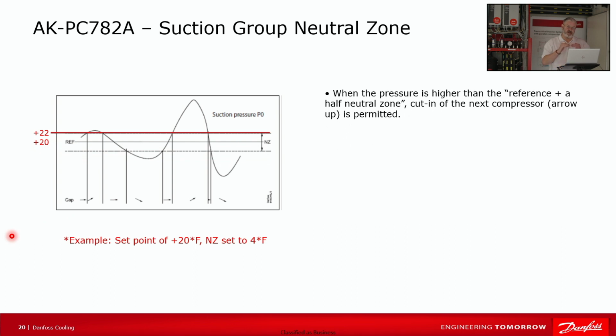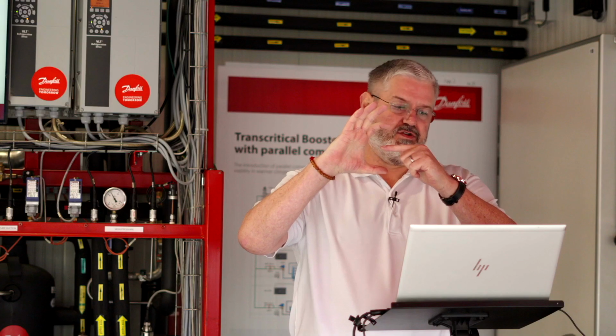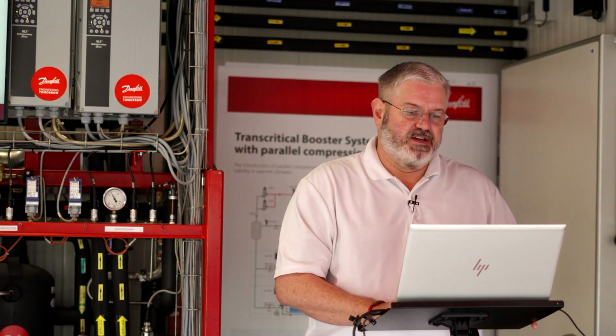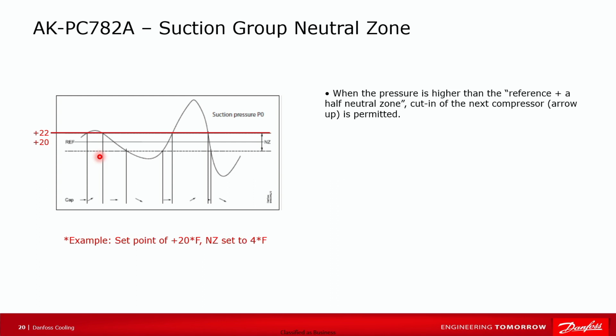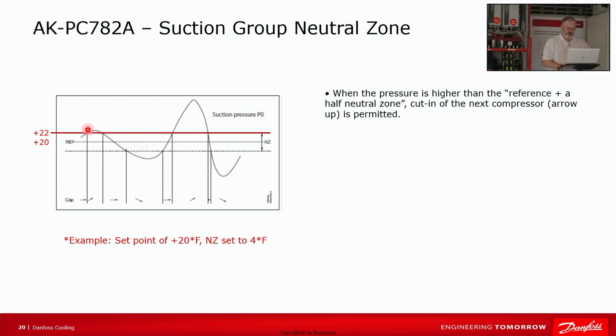So again, the neutral zone is like a deadband. It straddles the set point. We've got our set point here, and then we're straddling it with the neutral zone. If you reach half the neutral zone plus the set point, which we've done here at this point, we call that the plus zone. If you go to one of our controllers and look at a detailed status and you see plus zone, it means we're more than half the neutral zone above our set point. And plus zone means we're going to turn on the next stage of capacity.